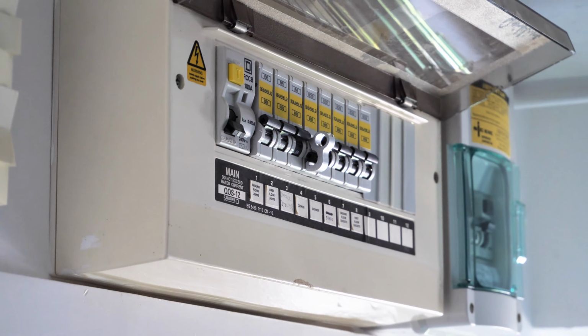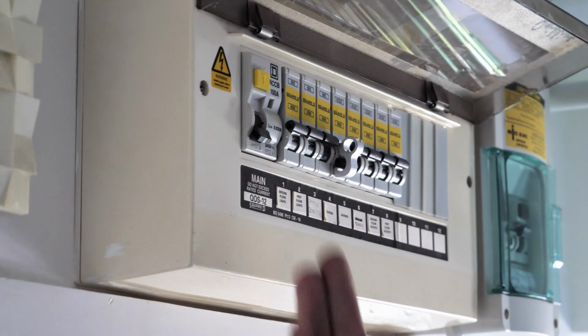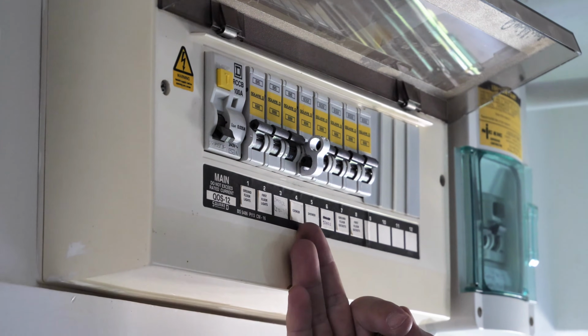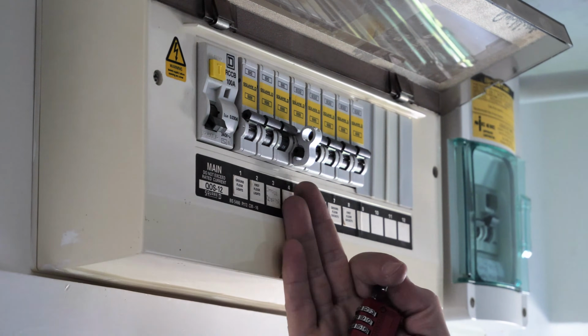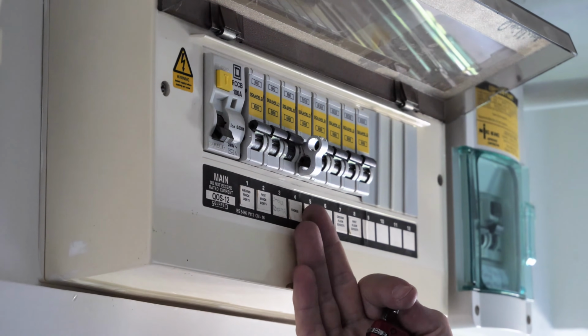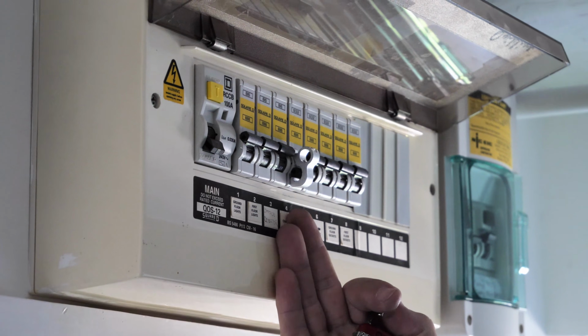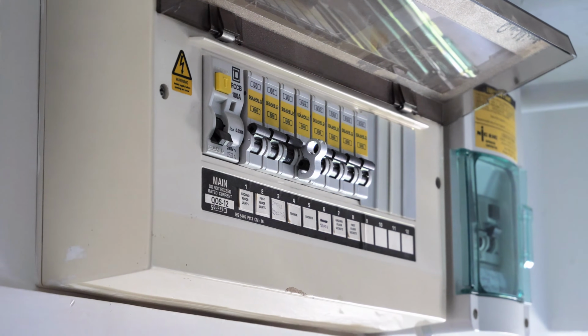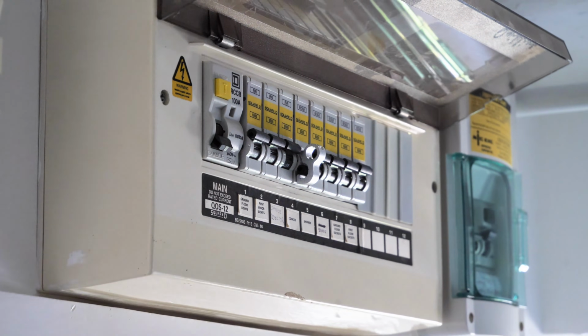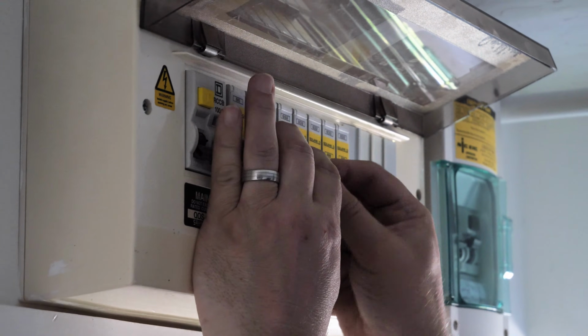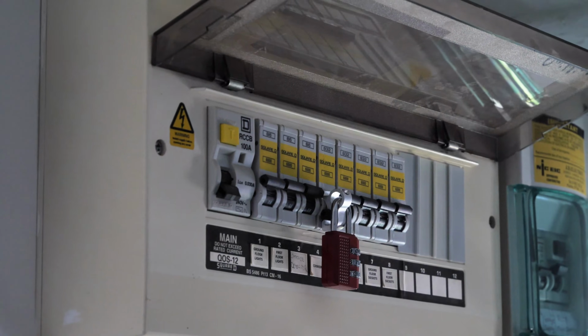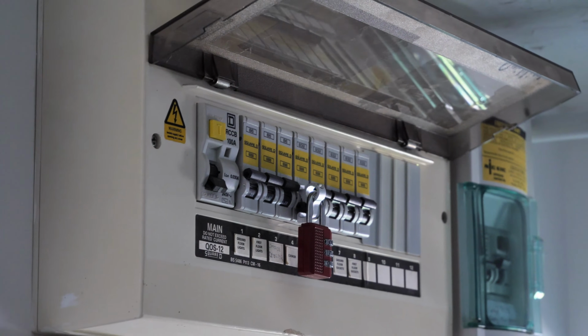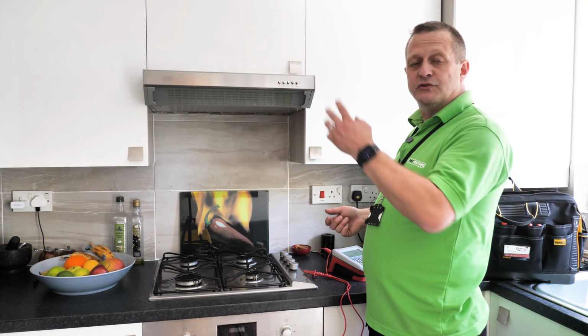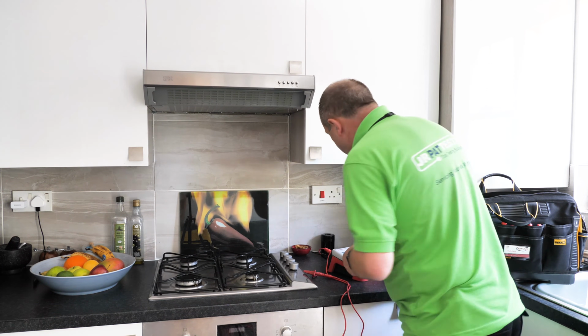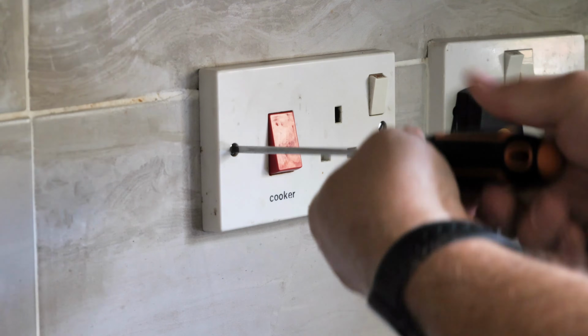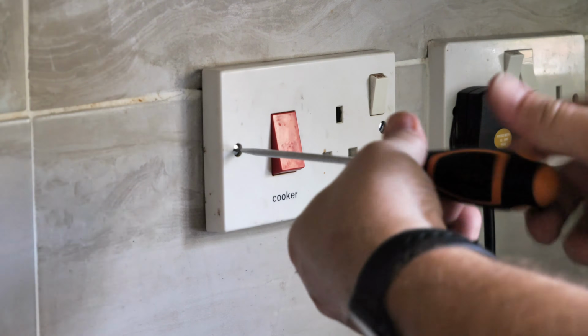We come to the consumer unit, and as you can see, I've isolated the power at the main switch and also on the cooker circuit, and I've already attached a piece of lockout kit that prevents that circuit from being re-engaged and coming live. To ensure that nobody can take it off, we then attach a padlock onto it, secure it, so that we know we are completely safe. Right, so now we've got the consumer unit isolated and locked off, we're going to see about removing the screws from the socket.